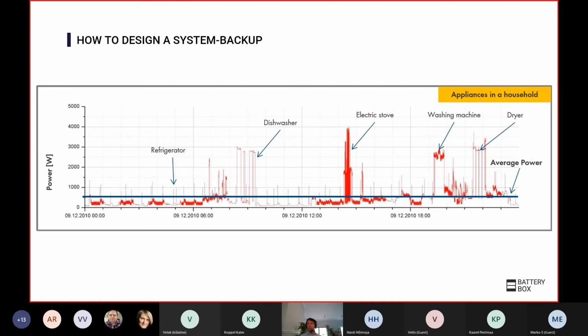In backup systems, it's less of an energy calculation and more of a power calculation. This graph shows the consumption of different appliances in a home that mostly just uses about 500 watts, a really low base load. But as soon as particular appliances like the dishwasher or electric stove connect, power consumption multiplies enormously, up to almost 5 kilowatts. This means that if you connect all appliances to the energy storage system in a backup setup, that system must be able to handle the big surge at the start of loads like dishwasher or washing machine motors.